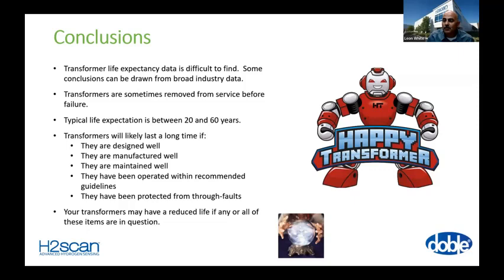And it's also important to note that a lot of people are focused on transformer failures, but you take transformers out of service for various reasons, not just for failure. They may be upgraded, or people are concerned about the age and so forth. But again, from the data that we found, age isn't necessarily an indicator that you should be replacing your transformers.